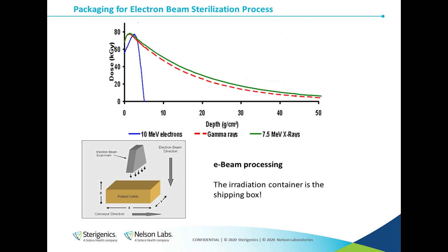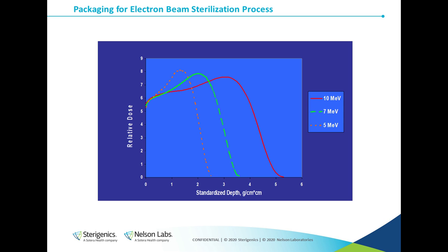One of the really nice things about the electron beam process is that the irradiation container is the shipping box. As depicted by the schematic on the left, the shipping container is conveyed under a focused beam of electrons, which scan across the box as it moves under what we call the scan horn. The box may only be under the beam for 10 or 15 seconds, for example, so the process for a single box is very fast.